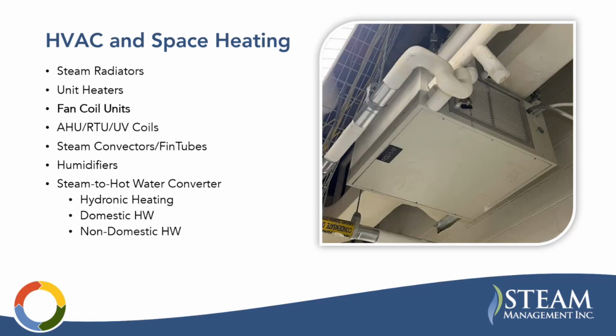This is a fan coil unit. It basically circulates air over a steam coil to control temperature as well. This is similar to a unit heater, however it's more for inside the occupied space of a building, typically has more sophisticated controls, and can be integrated into the building management system. So it's a similar idea of blowing air over a coil, but a bit different category of equipment.